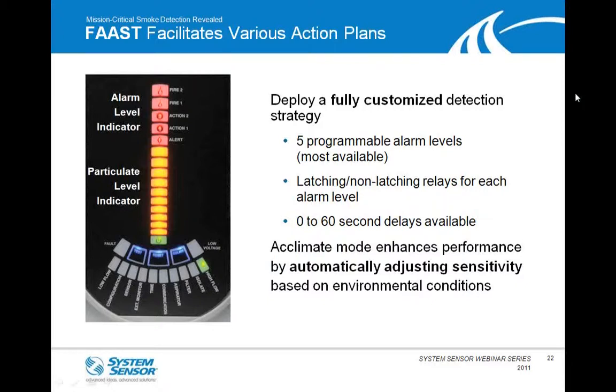Basically, FAAST offers 5 different programmable alarm levels. And again, if you look at the chart, it's a little hard to see, but that lowest alarm level is the alert level or the pre-alarm level. In addition to that level, there are 4 additional levels to set multiple action plans in place. Those relays associated with the alarms can be set for latching or non-latching. So for instance, for an alert level, maybe you want that to be a non-latching relay because it's just for supervisory. In addition, you can add 0 to 60-second delays on each one of those alarm levels.